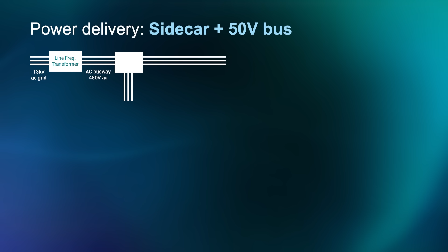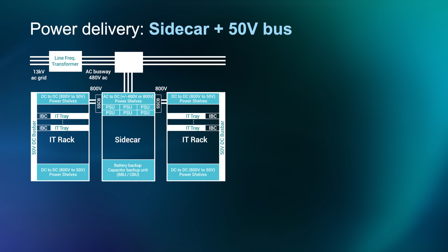can. And the way to do that is to introduce a sidecar rack. The AC to DC PSUs and battery backup units are removed from the IT rack and now placed inside this sidecar. This frees up valuable space in the IT rack to increase the overall compute density. Now, power is distributed from the sidecar to multiple IT racks at some higher DC voltage like 800 volts or plus or minus 400 volts.